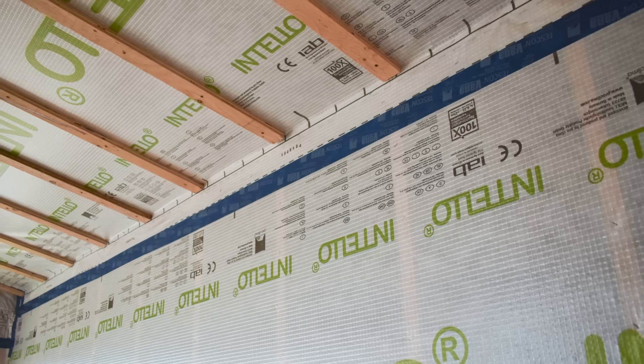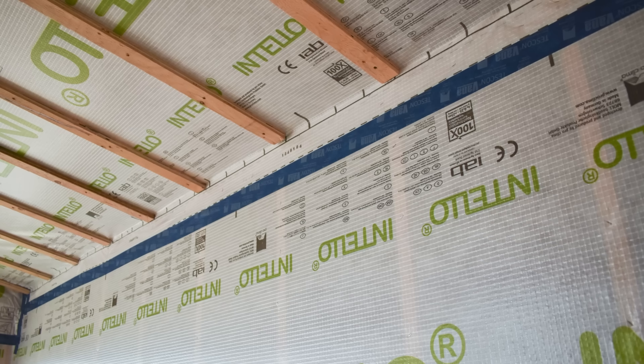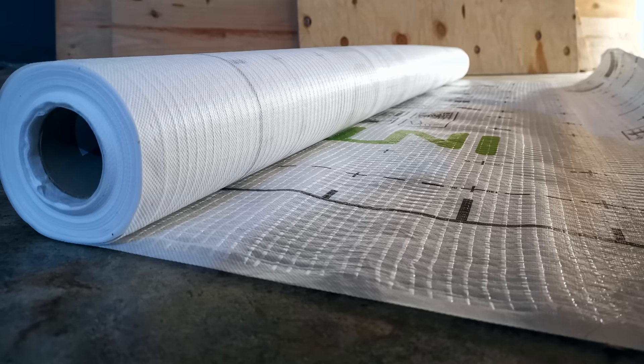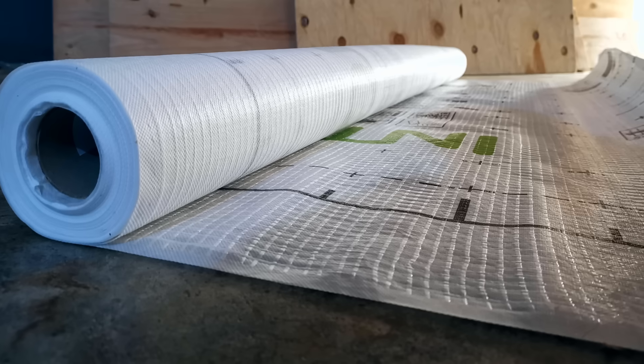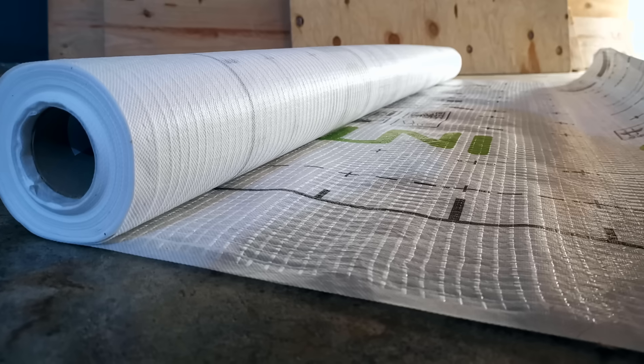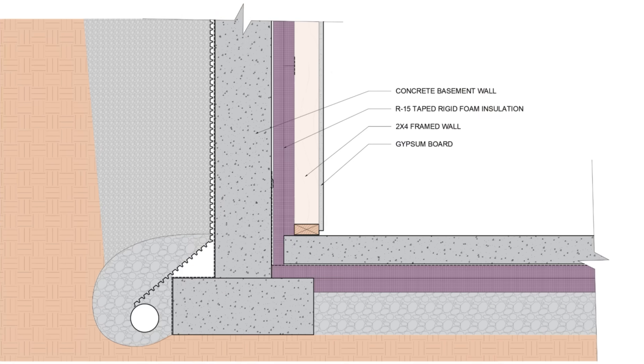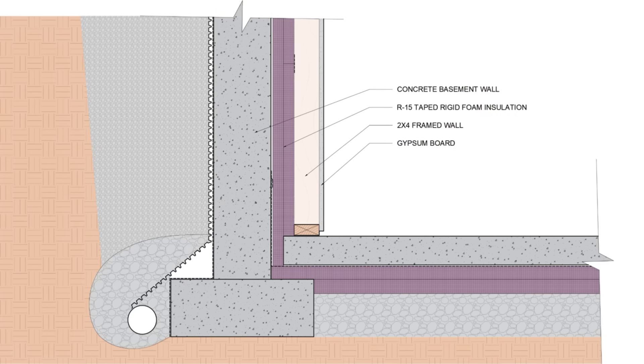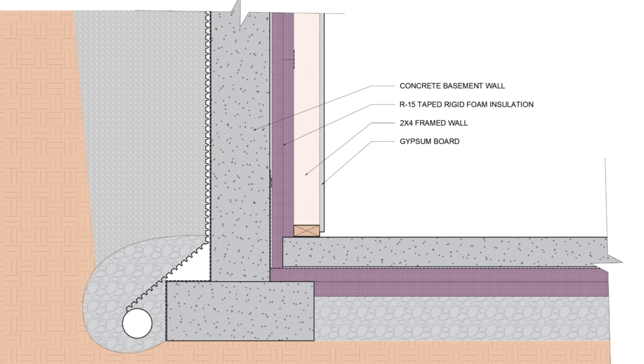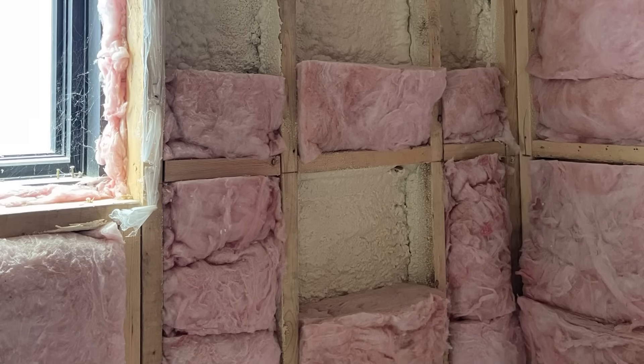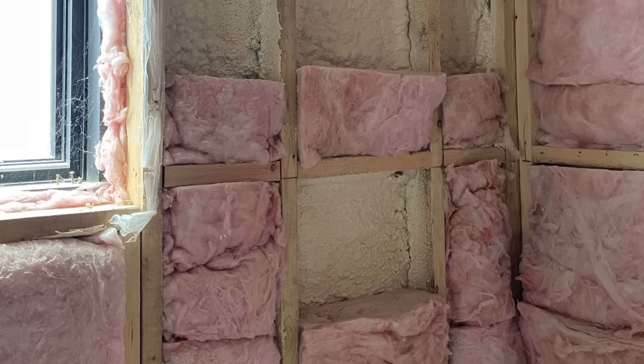Alternatively, use a fibrous insulation material with an airtight smart vapor retarder, which will prevent condensation but allow for drying back to the interior if things get wet. Inboard of that continuous insulation, we want the framed cavity on the interior side of that basement wall to either be uninsulated or insulated with a vapor-permeable insulation to allow for drying. We want our moisture-sensitive components to be able to dry out.